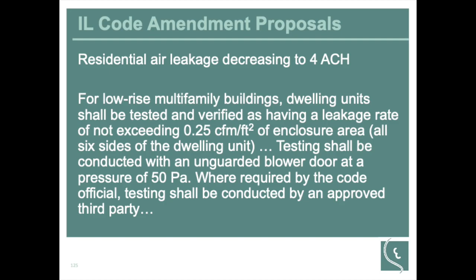Air changes per hour can skew things, particularly when you get into smaller units, because of surface area to volume ratios. So what they've proposed is adding an alternative air leakage testing for multifamily of 0.25 CFM per square foot of enclosure. Again, this gets to the meat and potatoes: I want the envelope to be sealed, so what I'm testing is how sealed the building envelope is, not air changes per hour, which is more about volume, did I build a good envelope?